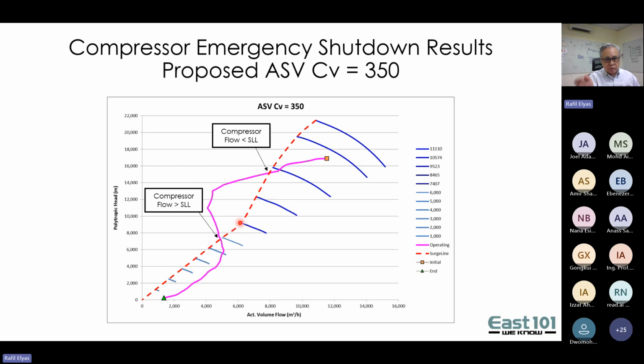Based on our analysis, we ran the dynamic simulation, and then we tripped the compressor at some point in time, and this is the trajectory. We've seen that it has entered the surge region. So there's an issue. Also, the time in the surge region is important. Some compressor vendors say you can stay there for a second or 3 seconds or something, depending on what speed you're at. Some compressor vendors will not allow for that. So it depends on your compressor vendor, your rotating equipment team, etc.